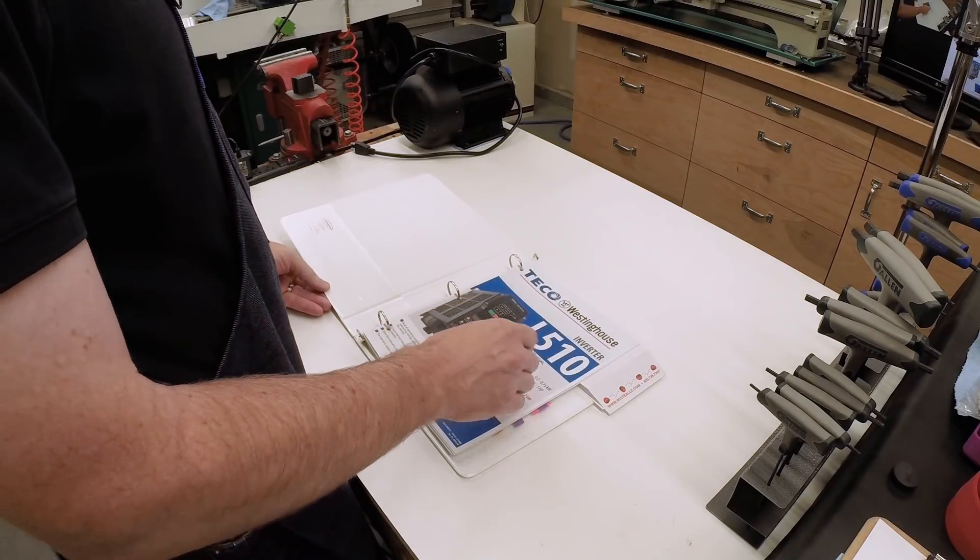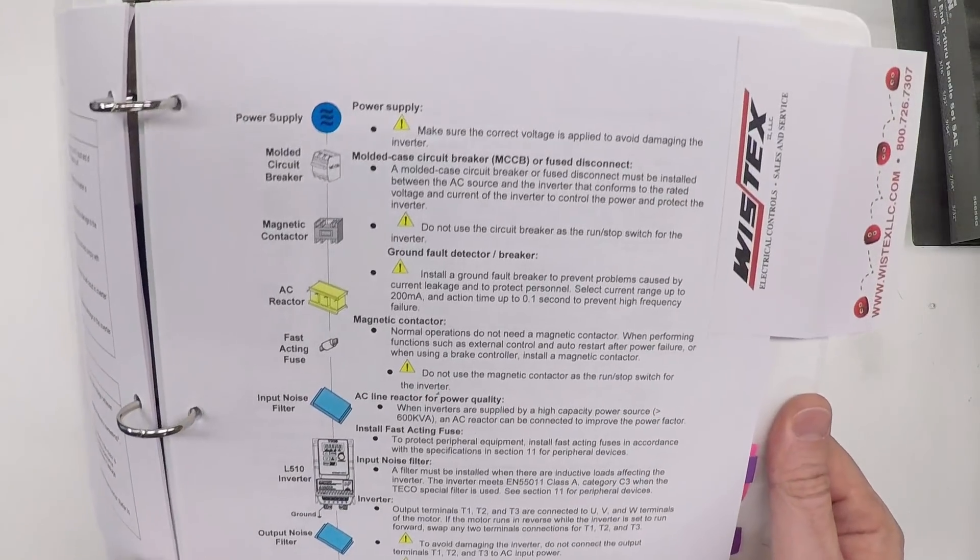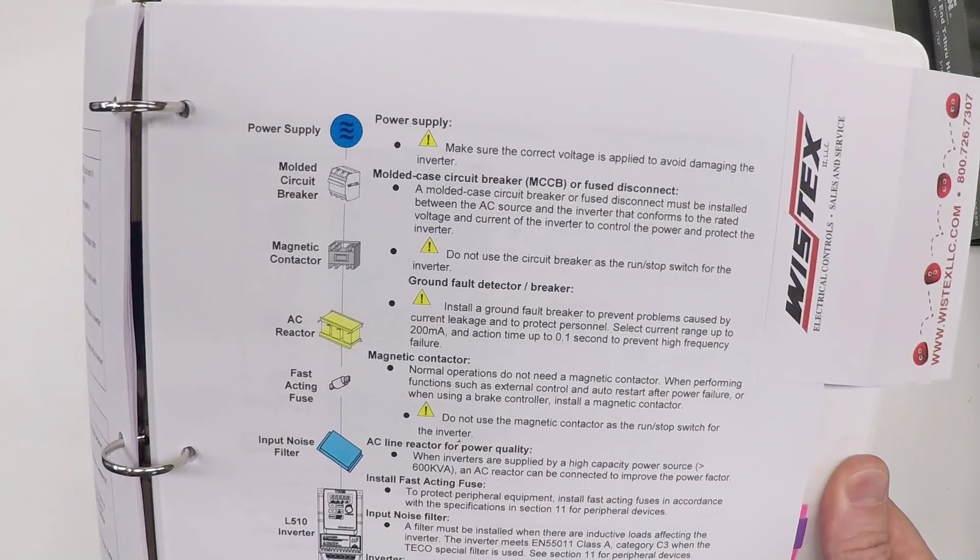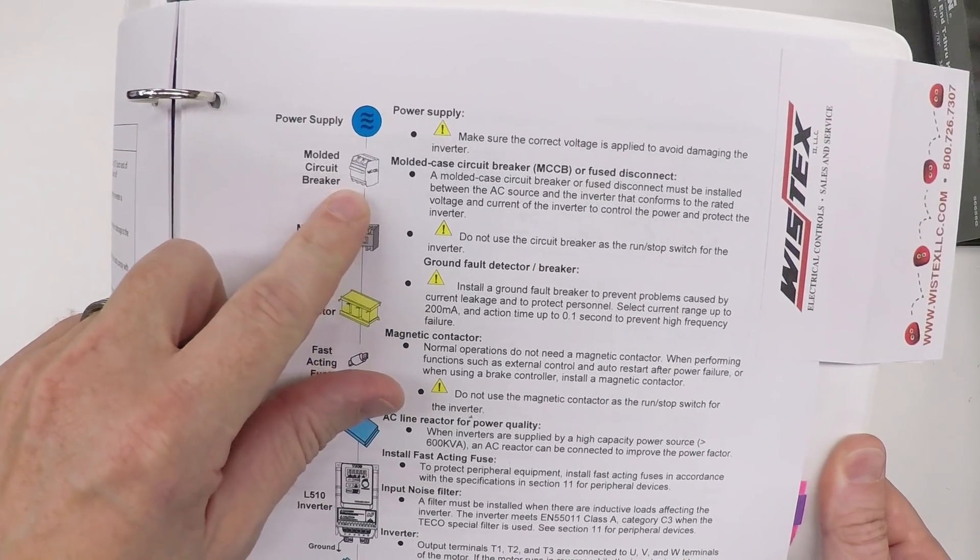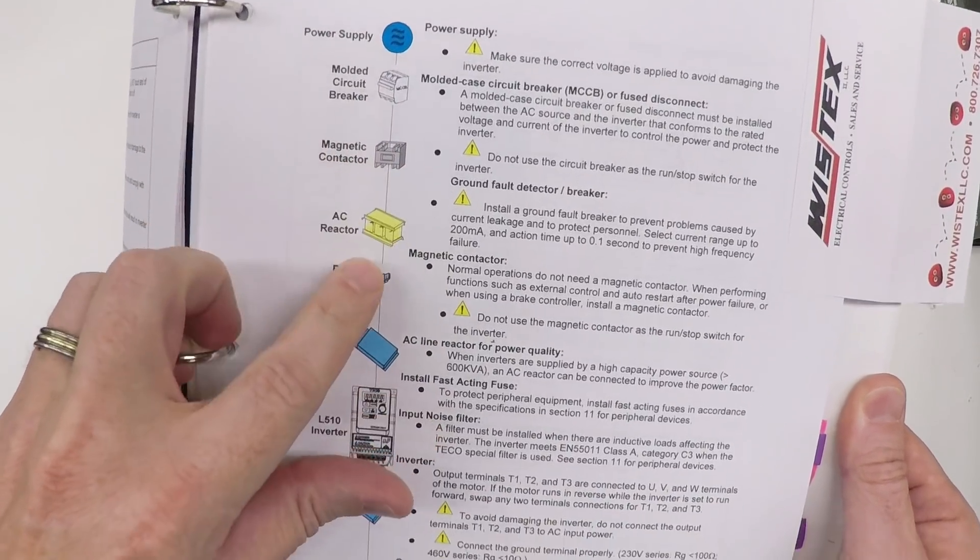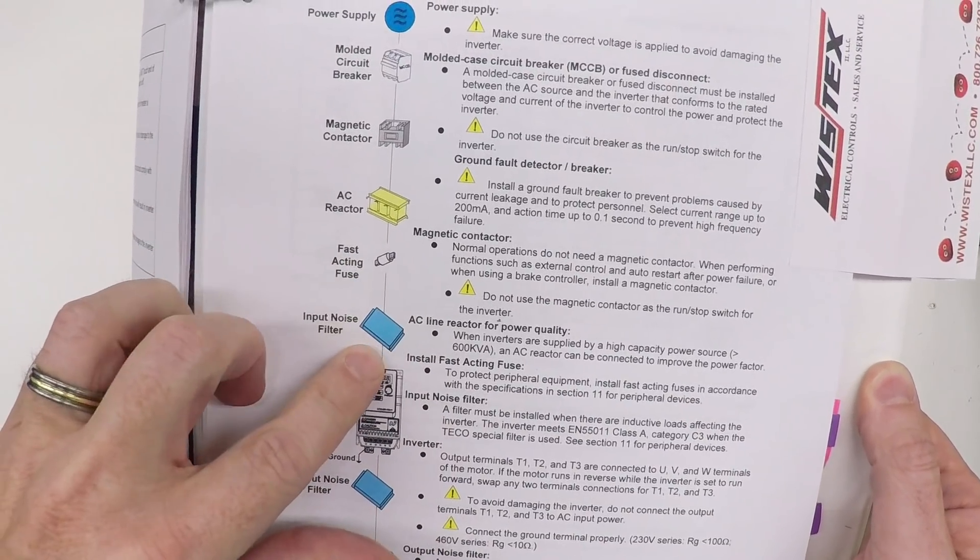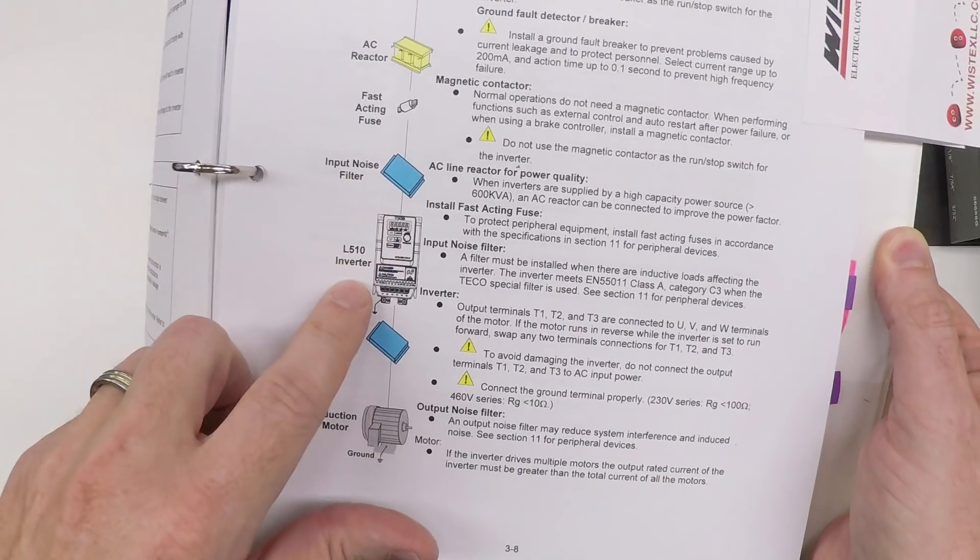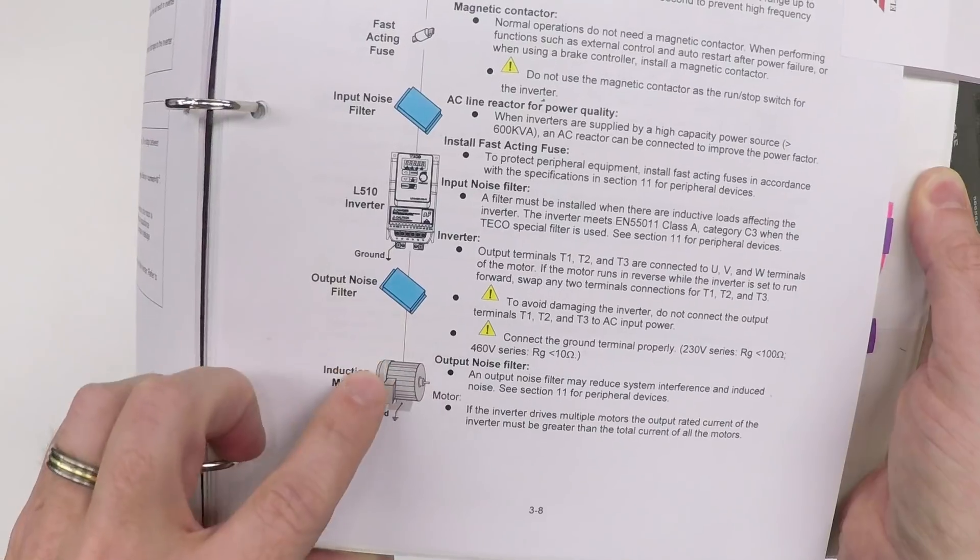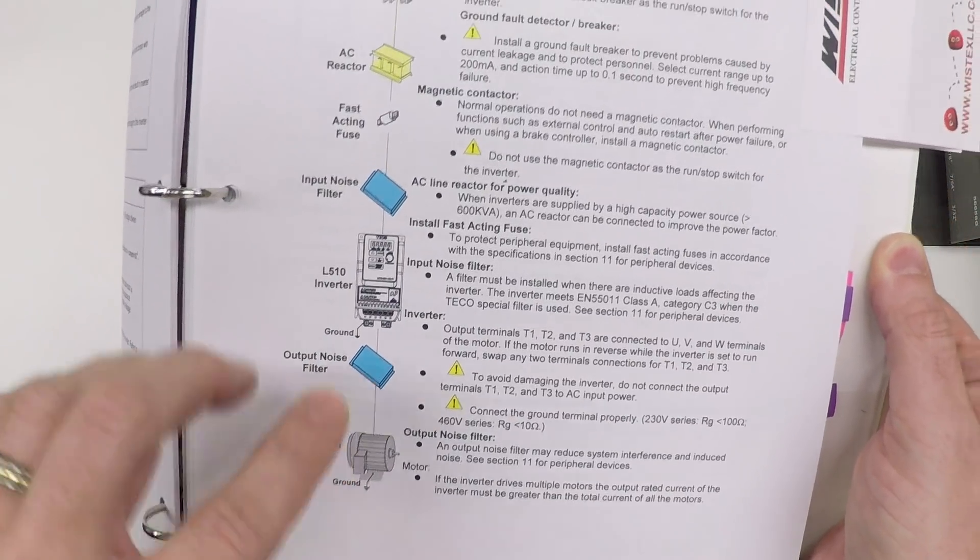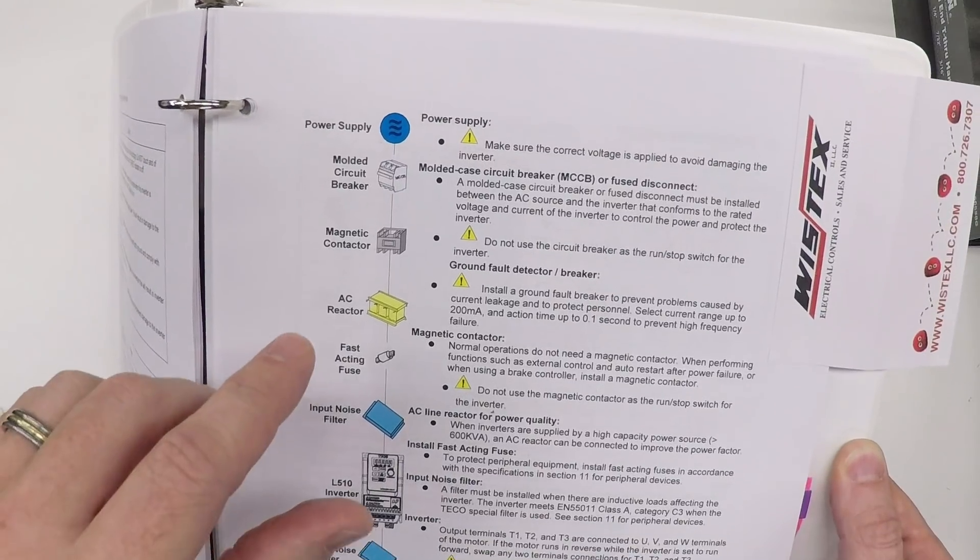This is the L510 VFD manual, and in the manual, they have a handy diagram showing how to connect it to power. Starting with the power supply, they recommend connecting it through a circuit breaker, a magnetic contactor, an AC line reactor, a fast acting fuse, an input noise filter, and then to the VFD. On the output side of the VFD, an output noise filter, and finally the motor.